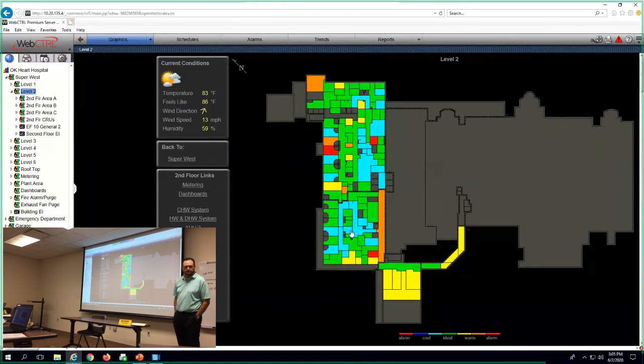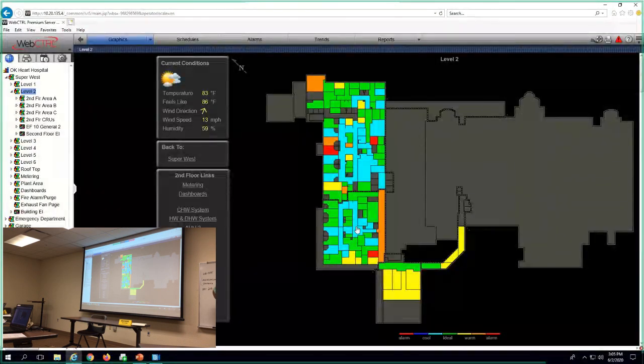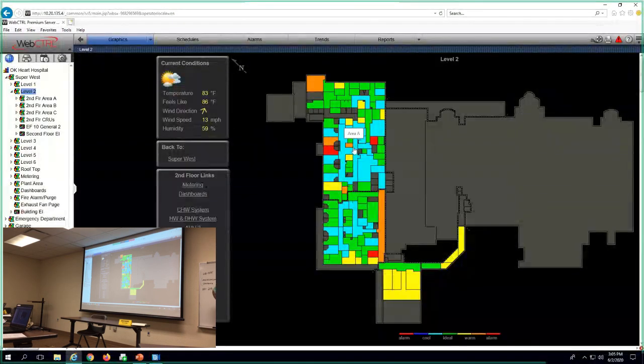We've talked about color a few times, and historically, in the existing building and in the MOB, one VAV may feed 3 rooms, right? So we often use that color sequence to link those 3 rooms to that one VAV. Yeah. If we're using this as a tool, then how could we identify 2 or 3 or 4 more rooms per zone? Good question.